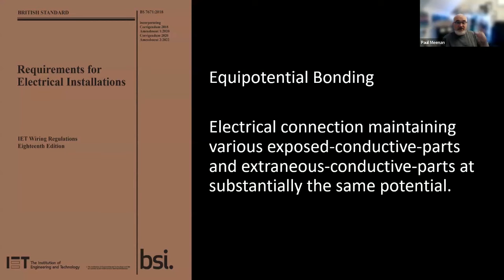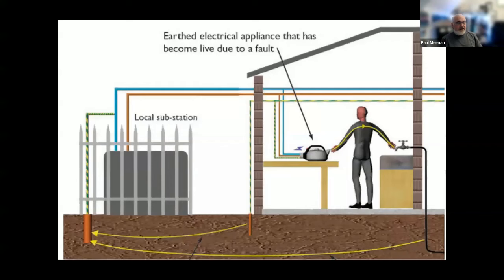So what we do is equipotential bonding. And equipotential bonding, or equal voltage, is the electrical connection maintaining various exposed conductive parts and extraneous conductive parts at substantially the same potential. We keep using the word potential, and it's my personal opinion it should be deleted and we should just use the term voltage.